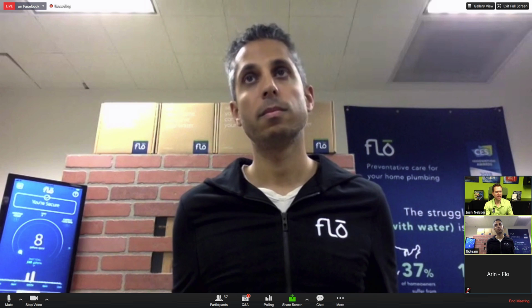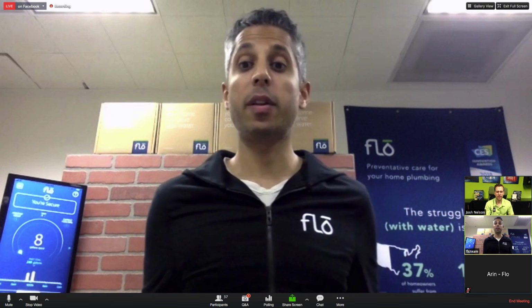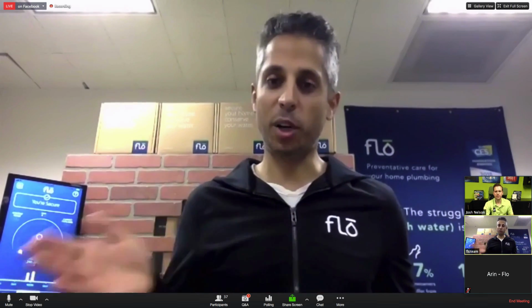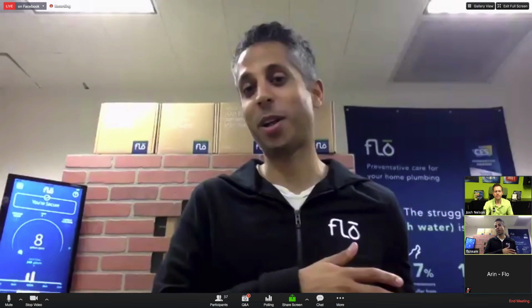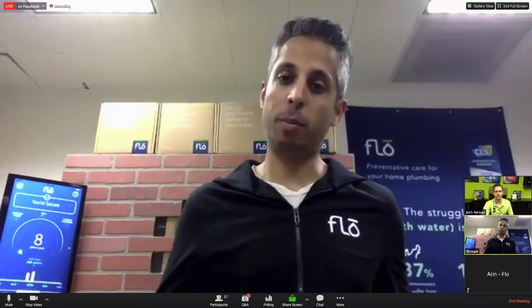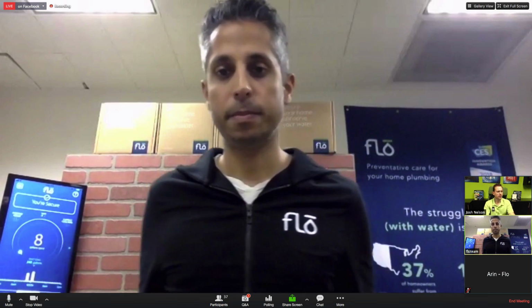And Matt Savas asked, and you may have just answered this, so I apologize, but does it need to be installed after the pressure regulator or before? We definitely recommend installing it after the pressure regulator, for the reason I just stated. A lot of people install pressure regulators and then forget they're there, taking for granted whether or not the regulator is working properly. Even the manufacturers recommend that you repair and maintain those every 5 years. People have had pressure regulators for 30, 40, 50 years, and they never know whether they're effective or not. So we recommend installing it after the pressure regulator so you can monitor how effective the regulator actually is. Great, good question.